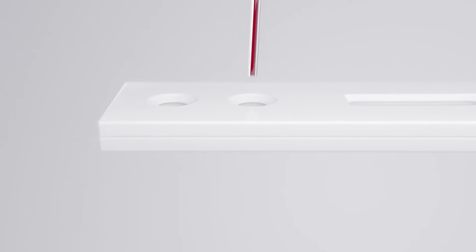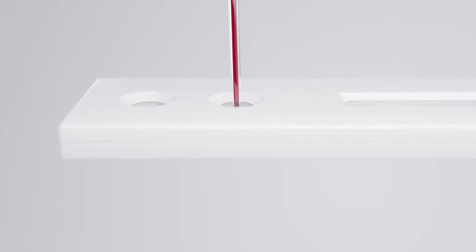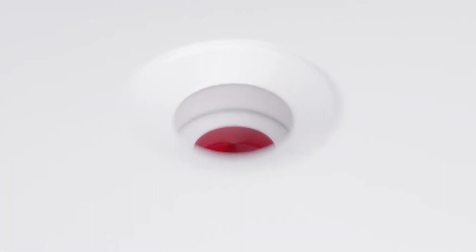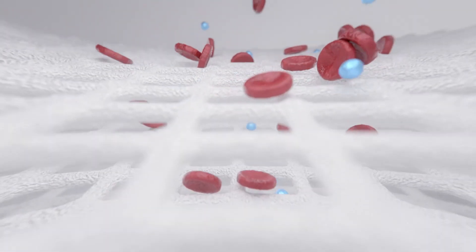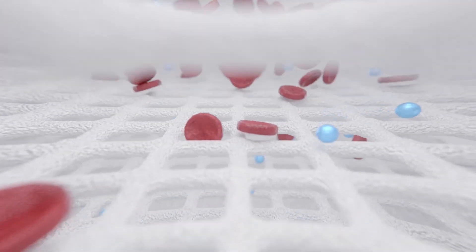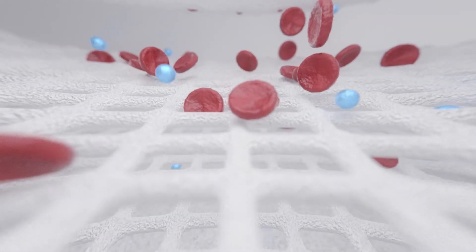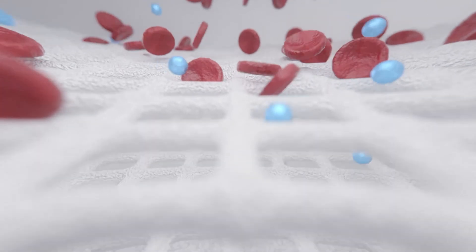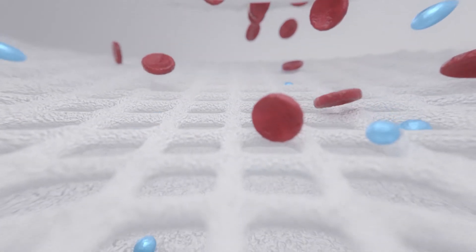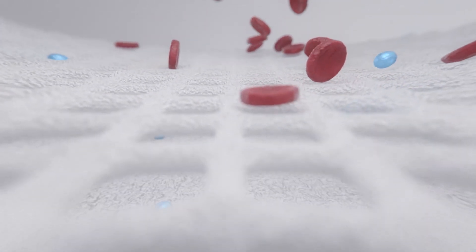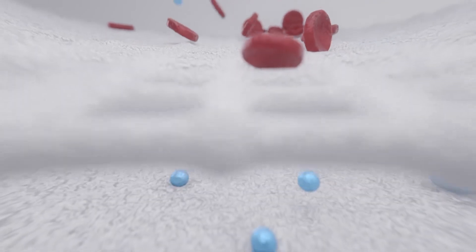For step one, a small amount of the required sample, in this case blood, is deposited into the sample well of the cassette. The sample pad at the start of the lateral flow strip filters out the red blood cells and other large molecules to aid the sample flow and reduce interference, while allowing the analytes of interest to pass through.